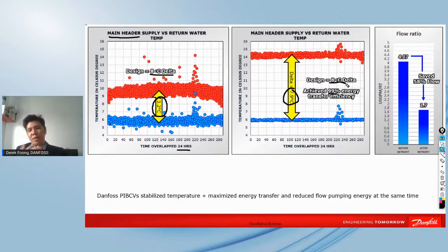Of course, when we stretch the delta and get very precise flow, this is a very good opportunity to actually reduce the pump speed, right? And this is where we connect the pumps to the critical unit, where we have a hydronic calculations team backed up with software to calculate and locate this critical unit. So we get to save 60% of the flow.